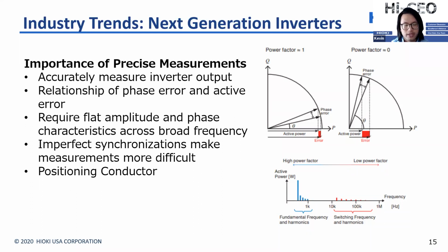So we have a graph here that shows the relationship between phase angle or phase error and active power error at different power factors. You can see that the voltage and current phase error in the measurement is greater on the active power at low power factors than at higher power factors. So in order for us to take accurate measurements of the active power at the switching frequencies and its harmonic components, we need testers that have both flat amplitude and flat phase characteristics, across a broad frequency band.